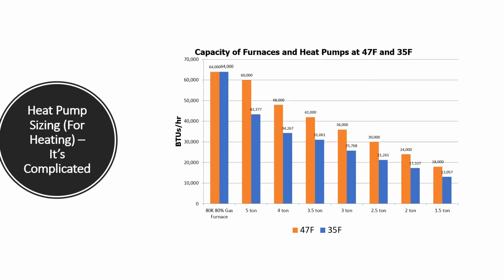So this chart just sort of reinforces what I said before, is that here we have a furnace in orange, and we can see at 47 degrees, it'll give you 64,000 BTUs. And sure enough, when it's 35, it gives you 64,000 BTUs. But a 5-ton heat pump at 47 degrees would probably give you something close to 60K. At 35, you're honestly down to almost a 3.5-ton unit. Let's look at a 2-ton unit over here. Sure enough, at 47 degrees, it's 24K. But by the time you get to 35, really you have a 1.5-ton machine.